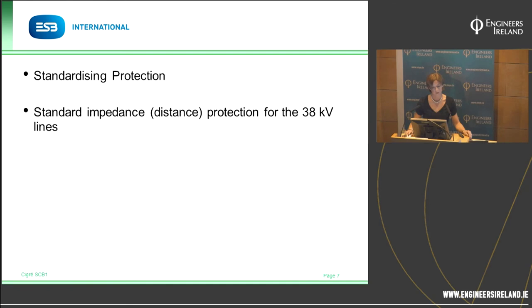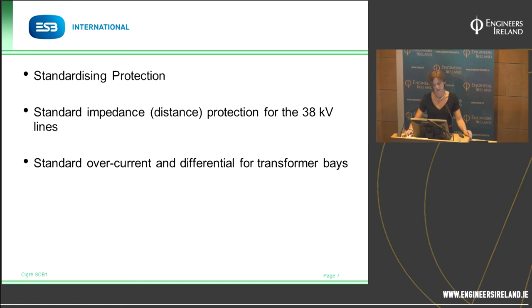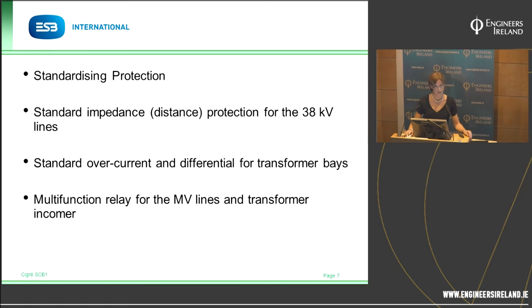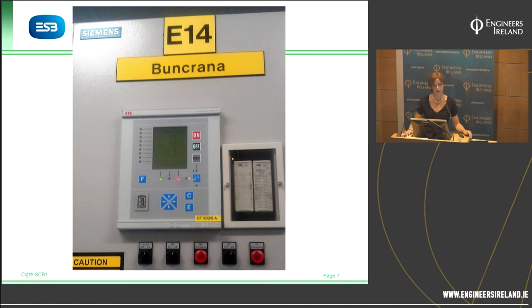The 38 kV line cubicles are protected by impedance relays, protecting the cubicle from faults on the line. The transformers are protected by overcurrent and differential relays, again protecting the transformers from current surges and internal faults. And we chose a multifunction relay for the MV side, which could protect either transformers or line bays. That's a picture of one there protecting a 20 kV line in Buncrana in County Donegal.